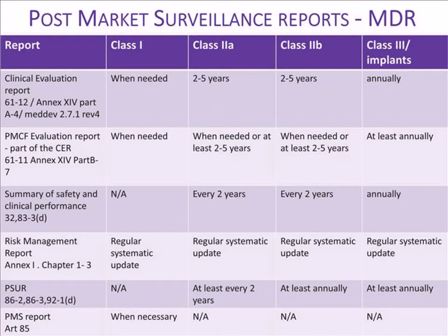Now, the complexity, and I'm sure you came to the conclusion at this stage of the presentation, is number one, the overlap of the various reports. As we've seen, these reports, which are separate and need to be produced and sent to different entities, are vastly overlapping. Number two, the periodicity of each of the reports is not the same. So this creates a challenge to maintain the various reports in full synchrony. So when you produce a PSUR, make sure that you have included the latest information of the clinical evaluation reports, and so on and so on.